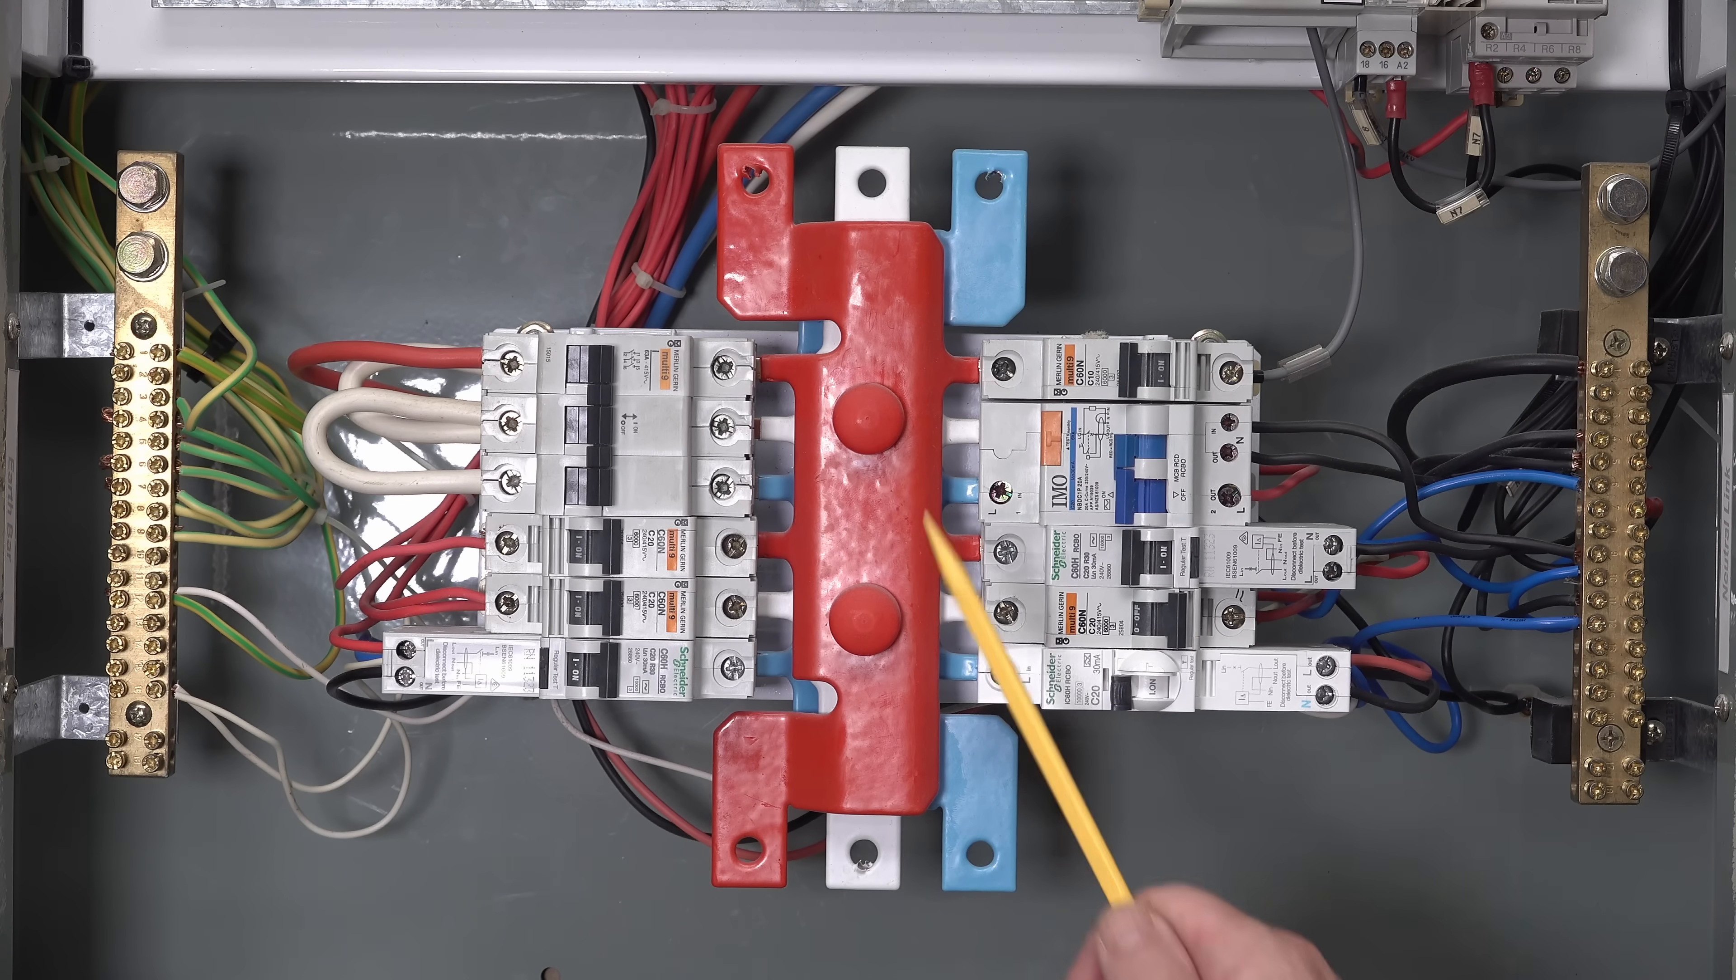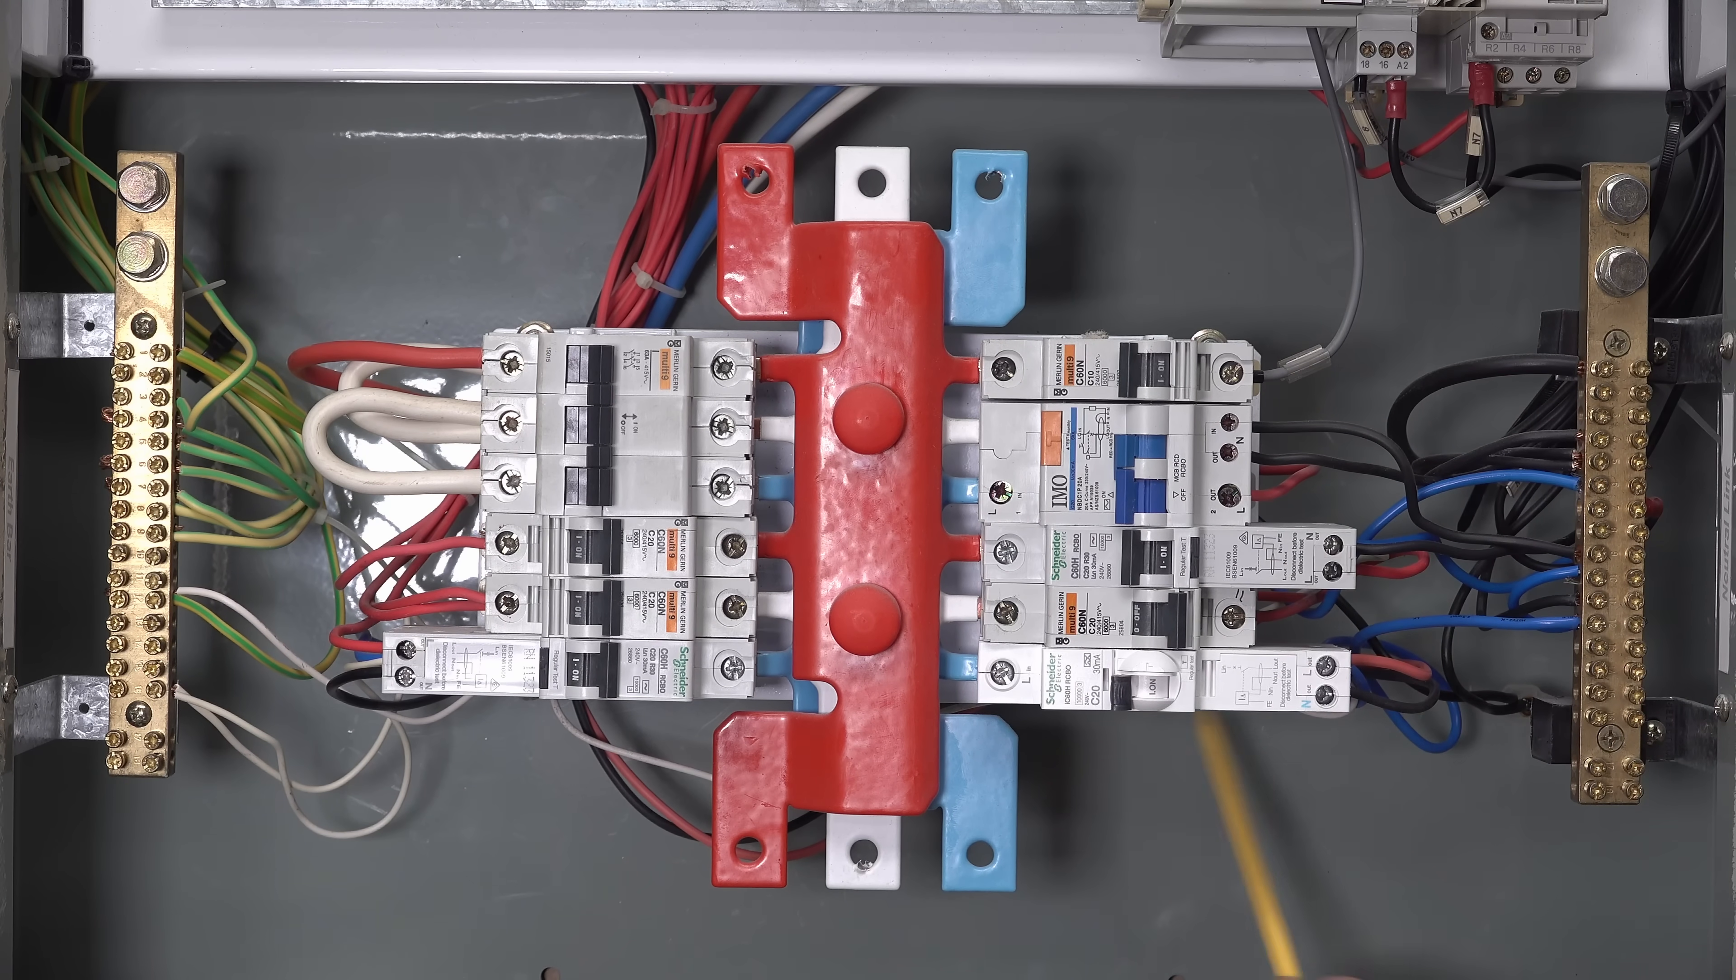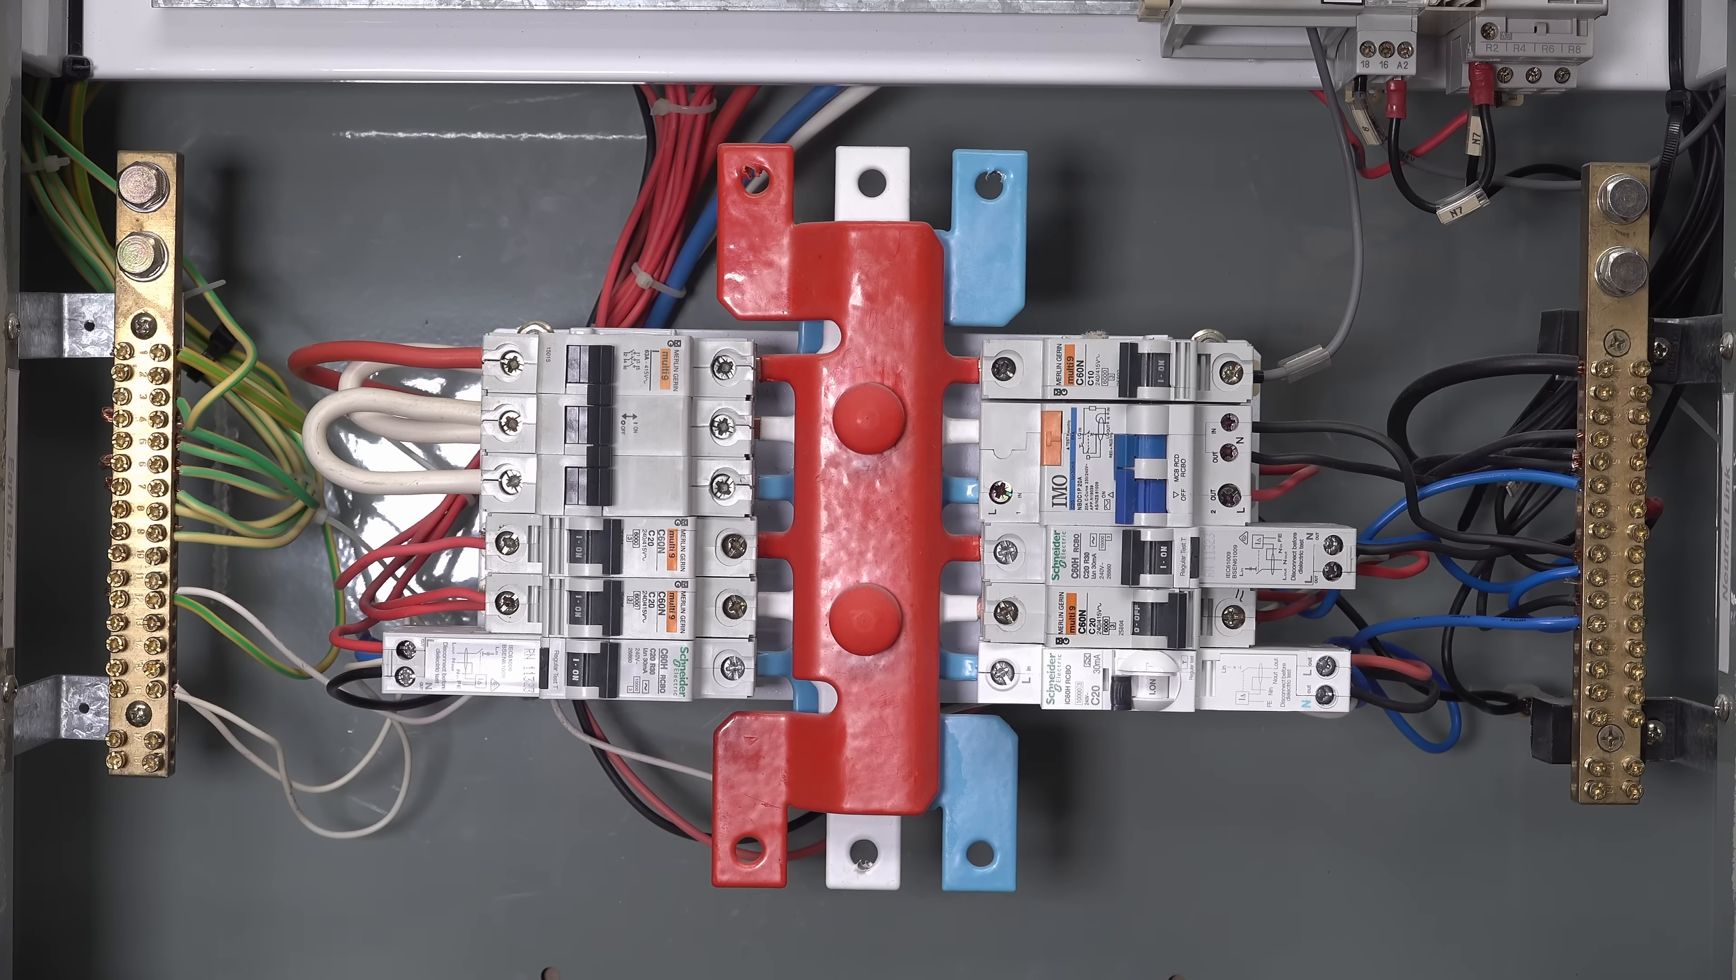So that's really cool. So I hadn't actually remembered that from the last time I poked in here. Anyway, there's just some vertical DIN rails behind here, some very large spaces like 10 centimeters or something off the rear wall there. We've got our neutral block over here, and we've got our earth block over here. Apart from that, it's pretty basic. Here's our main neutral link coming in over here. Here's our main earth link. You can tell by the diameter of the cables there.